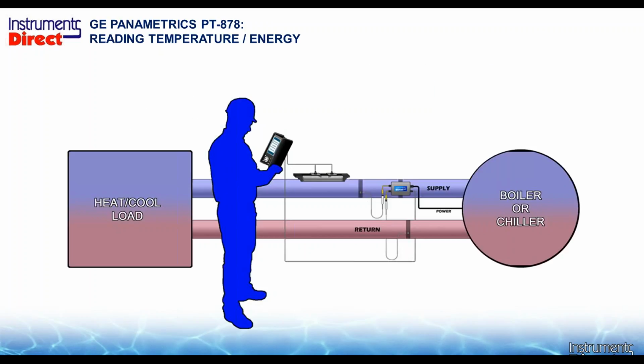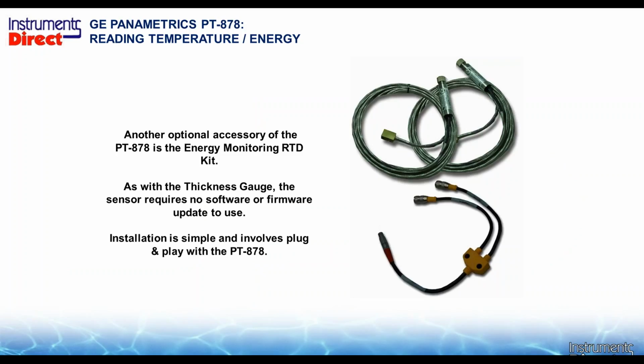Energy applications. Well, some people will like to use this for flow and energy. If you have an energy application, you can't beat this for getting survey information from a log to manage your chilled water, your hot water, your cooling application. Do I need to put a new chiller in there? To make a dynamic impact on the use of other technology by doing a discovery process with an energy survey. So what do you have? Well, you've got the same PT878. Now we need to add temperature.